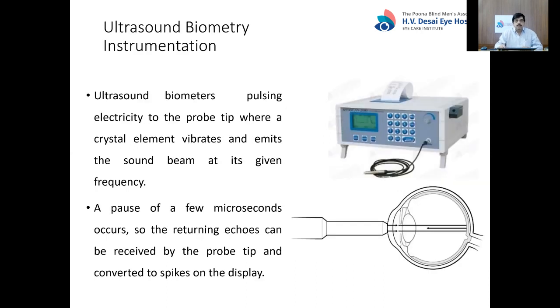Looking at the instrumentation, ultrasound biometers come in different sizes and shapes. The console is a box with electronics inside and a printer, with a display that may be a touchscreen or normal display with buttons. The biometer supplies pulsing electricity to the probe tip, where a crystal element vibrates and emits a sound beam of 10 megahertz. A pause of a few microseconds occurs so that the returning echoes can be received and converted to spikes on the display.